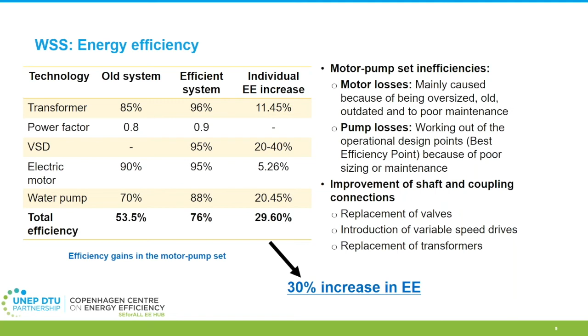Similarly, for pump systems, depending on the desired flow-head combination, you can define what kind of pump you need and what design rated details are required. So yes, the initial investment may be high, but compared with the yearly losses, and adding regular maintenance costs, it would eventually justify that investment in energy-efficient systems is inevitable.